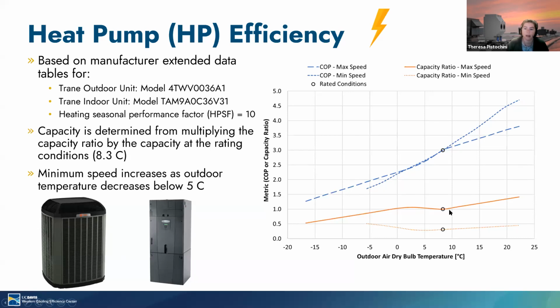The capacity of the heat pump at any outdoor air temperature is the capacity at the rating condition, here the black dots, multiplied by the capacity ratio at that outdoor temperature. So the heat pump can run at any speed between the minimum and the maximum speed required to meet the modeled load. When conditions allow, the heat pump runs at a lower speed to achieve a higher efficiency. For colder outdoor air temperatures, the COP starts to approach 1, which is the efficiency of electric resistance backup heat. When the heat pump at maximum speed cannot meet the load, the electric resistance heat works in series with the heat pump. At negative 18 degrees Celsius, the heat pump switches off and the entire load is met by the electric resistance heat.